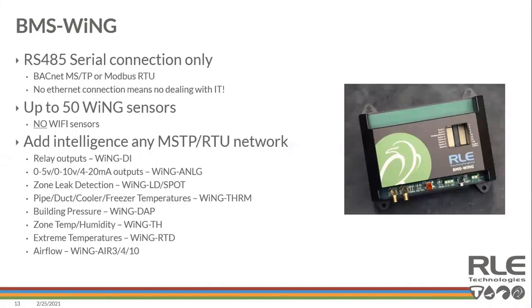I mentioned this product earlier, and I wanted to spend a moment on it because it's such a great way to add wireless to any environment that can connect BACnet, MSTP, or Modbus RTU. We've seen intelligence added to different environments where generators or other mechanical equipment have relay outputs that trip. We've taken our analog transmitter and connected 0 to 5, 0 to 10, 4 to 20 milliamp outputs of literally any sensor on the market. As long as it produces that output, we can take that data point and pass it through and integrate it so your optimization goals are achieved.